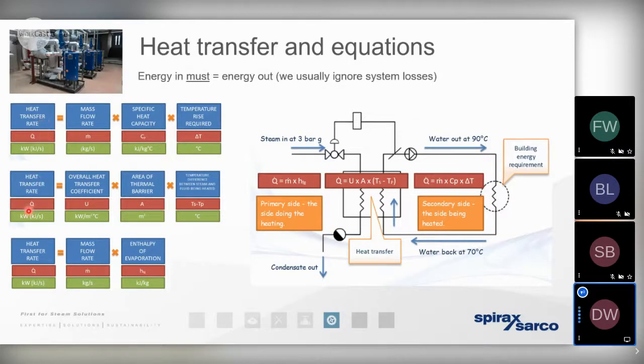So the next equation, which is also demonstrated here in the middle of the P&ID, tells us how we calculate the rate of heat transfer, the speed of heat transfer. And that's critically important because it helps us to understand how to correctly size the heat exchanger itself. And we can find the heat transfer rate, or the Q value, by multiplying the heat transfer coefficient. That's the U value, the speed at which the energy will move from the primary side to the secondary side.